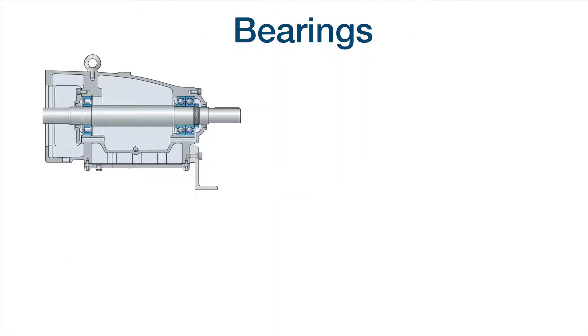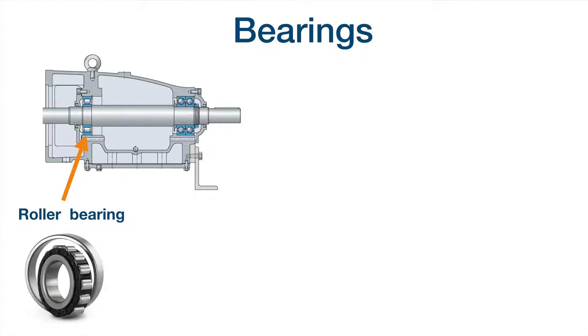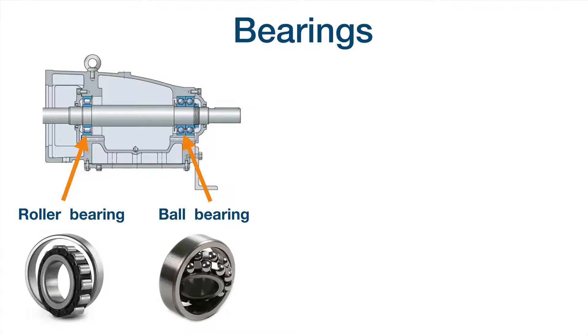Bearings: the function of bearings is to support the rotating shaft and all loads generated due to the rotation of the shaft — the forces involved in a rotating machine. Here we have a roller bearing, composed of cylinders, and this is a ball bearing. The lubrication of bearings is a very important issue. For example, roller bearings and ball bearings can be lubricated by grease. Bearings are normally sealed to avoid leakage or the entrance of dust.